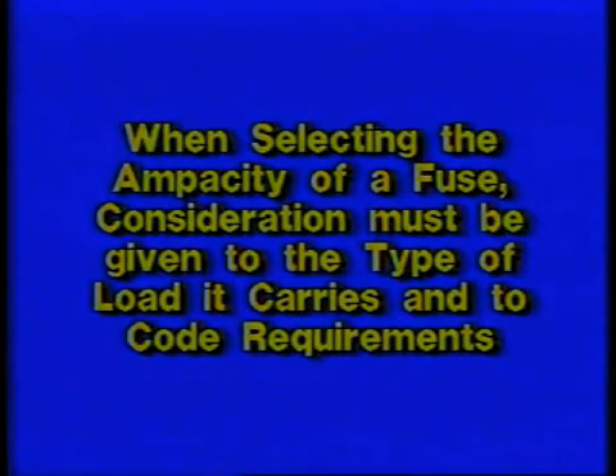If a fuse is used that has a voltage rating lower than the circuit voltage, arc suppression will be impaired. Under some fault current conditions, the fuse may not safely clear. All fuses have specific ampere ratings.